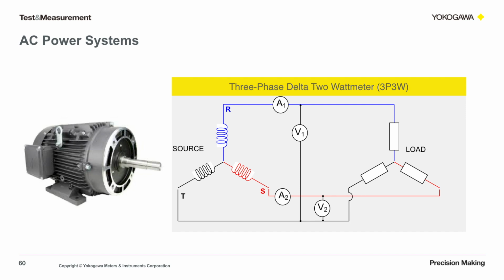A variant on a wiring technique when three voltages and three wires are present is the three-phase delta, but using two wattmeters, the 3P3W method. This method reduces a voltage and current meter and can calculate the third based on Blondel's theorem. This is less expensive because it requires one less wattmeter. Blondel's theorem states that the total power is measured with one less wattmeter than the number of wires. Since we have three wires in this system, 3W, we can measure the power with two meters. There's a derivation of this, but we're not going to cover it in the webinar.